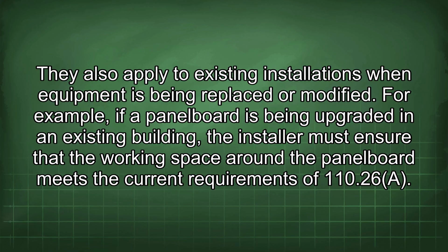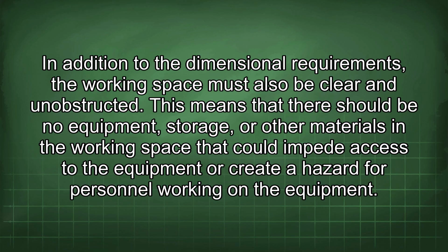For example, if a panelboard is being upgraded in an existing building, the installer must ensure that the working space around the panelboard meets the current requirements of 110.26(A). In addition to the dimensional requirements, the working space must also be clear and unobstructed. This means that there should be no equipment, storage, or other materials in the working space that could impede access to the equipment or create a hazard for personnel working on the equipment.